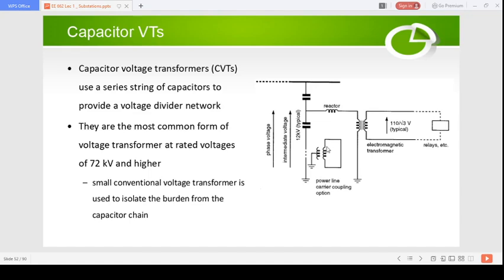Then you use a small conventional voltage transformer to isolate the burden, the load, from the capacitor chain. So you have a capacitor chain in series, basically building the capacitor or potential divider, and then for isolation purposes you use a small conventional voltage transformer. So nothing to do with the measurements.